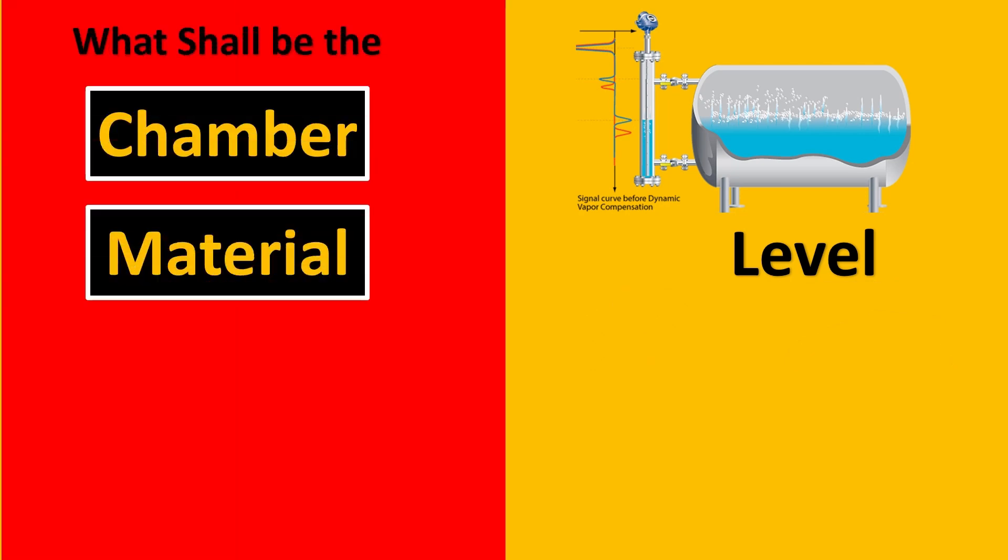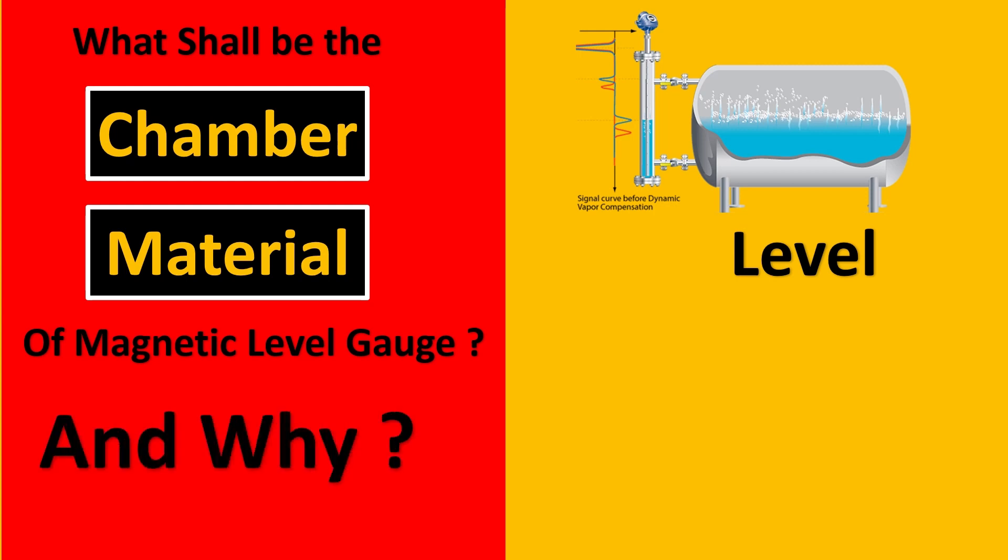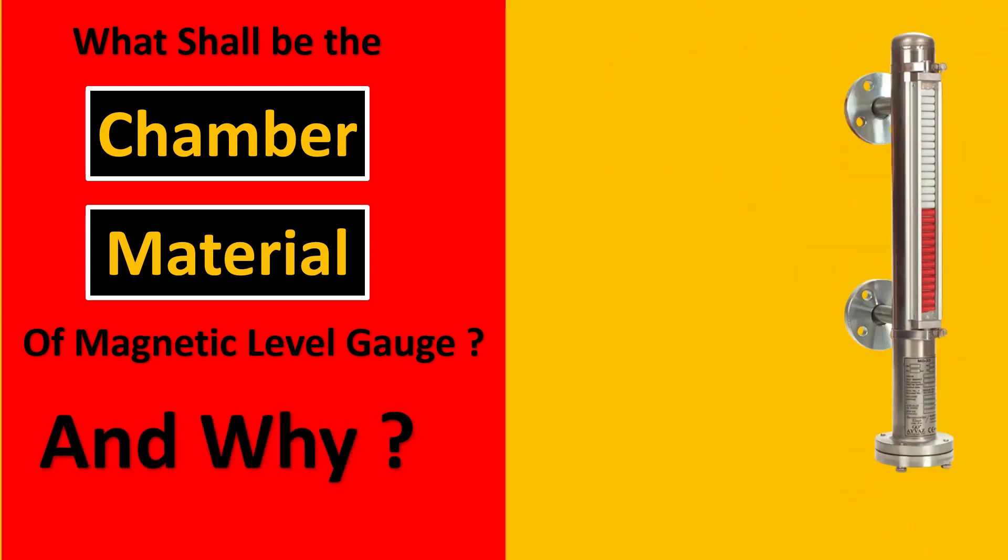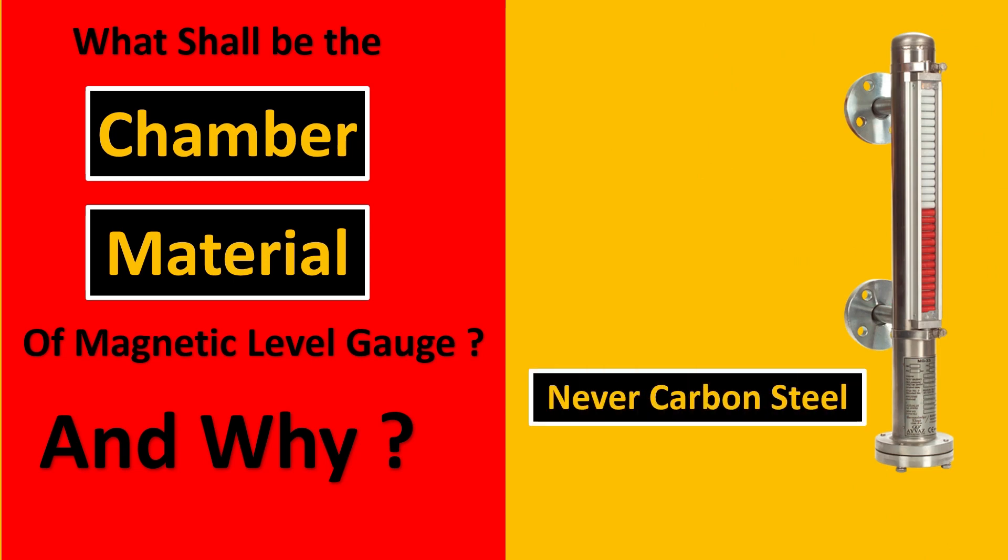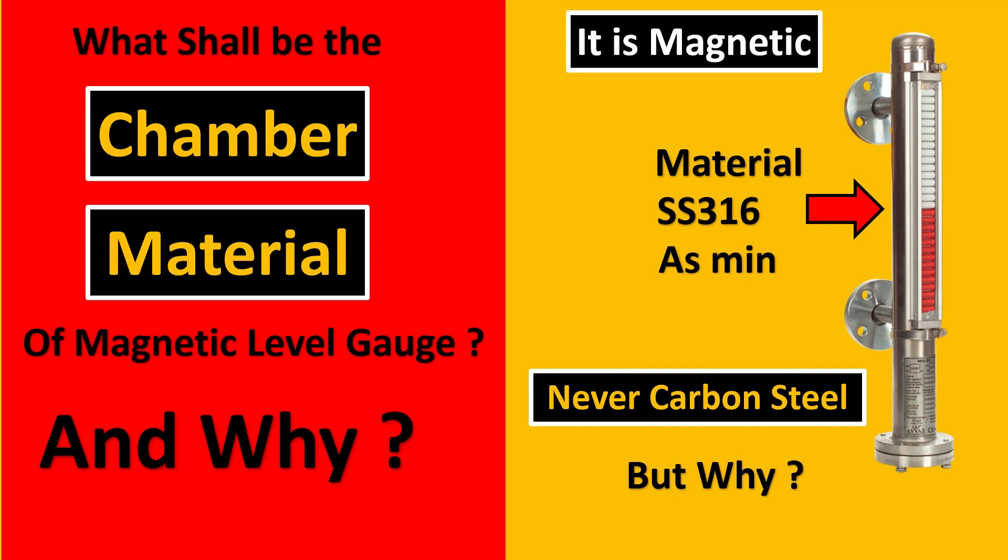First is what shall be the chamber material of magnetic level gauges and why is this special? So in the chamber of magnetic level gauges shall never be carbon steel. The material would be either SS316 as minimum or something higher. Maybe Hastelloy etc but never carbon steel. But why is this case? Because carbon steel is magnetic in nature and can interfere with our measurements. So as instrumentation engineers, we must recommend there should be minimum SS316.